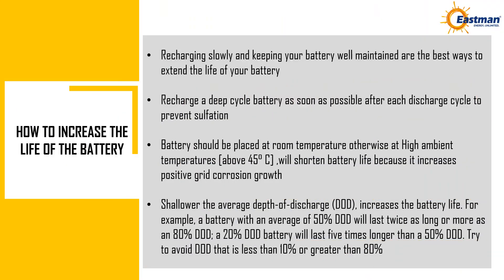How to increase the life of the battery? Recharging slowly and keeping your battery well maintained are the best ways to extend battery life. Recharge a deep cycle battery as soon as possible after each discharge cycle to prevent sulfation. Battery should be kept at room temperature; high ambient temperatures above 45°C will shorten battery life because they increase positive grid corrosion growth. Shallow average depth of discharge (DOD) increases battery life. For example, a battery with an average of 50% DOD will last twice as long as one at 80% DOD, and a 20% DOD battery will last 5 times longer than a 50% DOD battery.